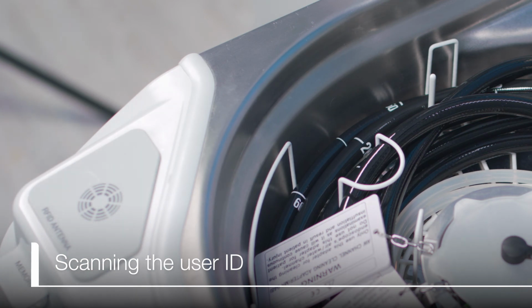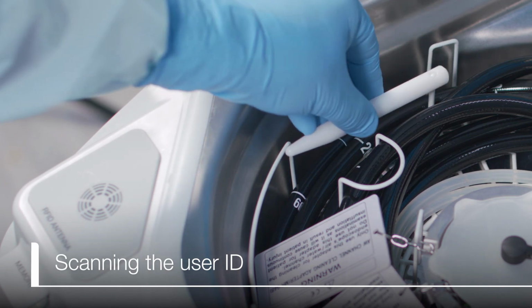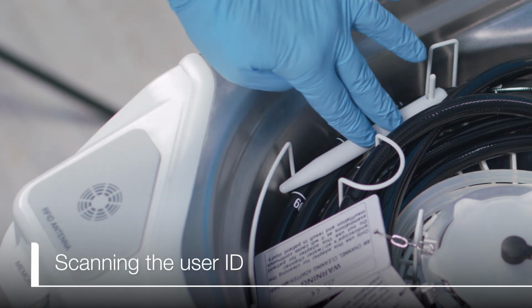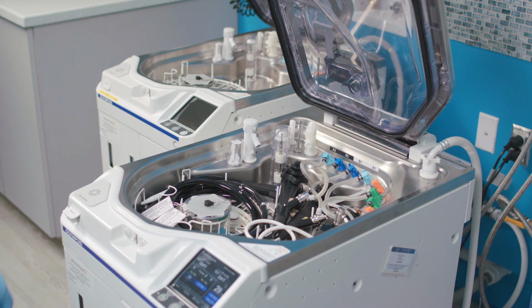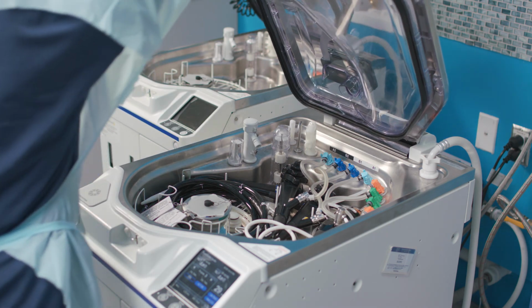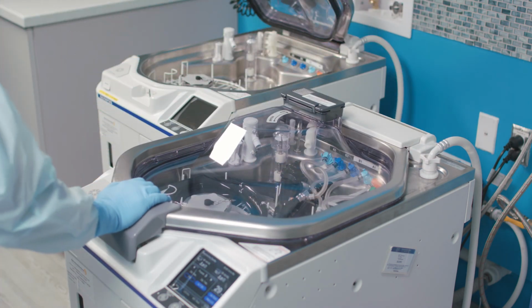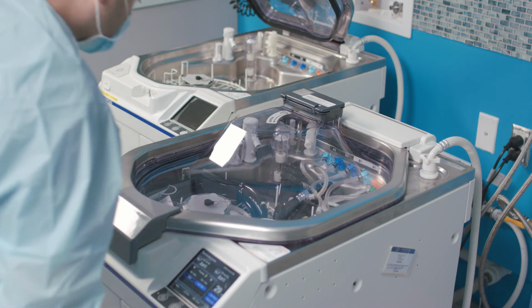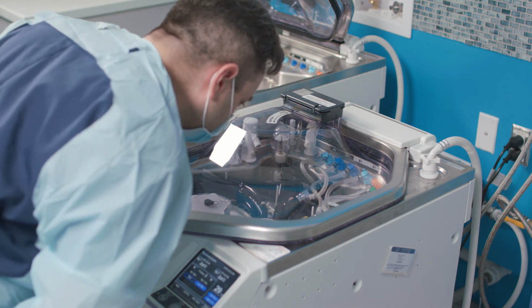Set the stylus pen on the ring of the retaining rack. Now that both scopes are loaded inside the OER-Elite, close the lid and check to ensure that the lid is not touching any portion of the endoscope.